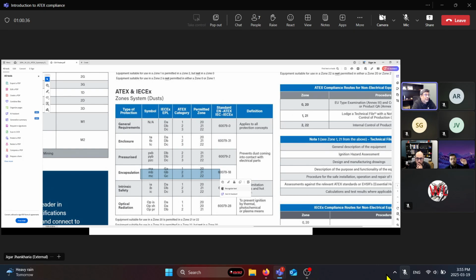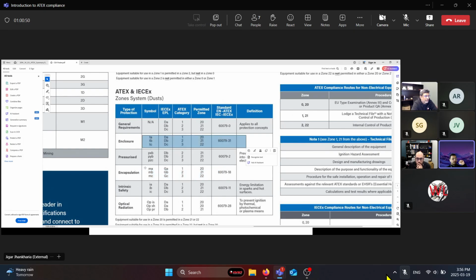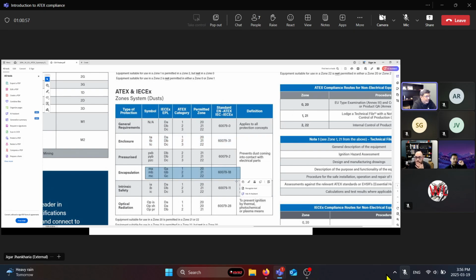Oh, is that what that means? So something like an enclosure that seals around? No. If you use an enclosure, then you're going to have to look at this method of protection. But if you're talking about encapsulating all the electrical components inside your tool, then we can look at encapsulation. Okay, sorry, I should have said enclosure, not encapsulation. So if we go with an enclosure, it could satisfy 21 and 22. Correct, but there is one main condition.